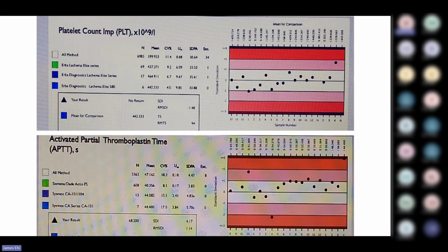I had to stop running patient samples until this was resolved, because it affected the reagent, not just the control material. By the time I used the internal control and the external control, everything was failing. So at that point, I had to outsource until I got a new set of reagents. So don't say it has not been delivered to me.